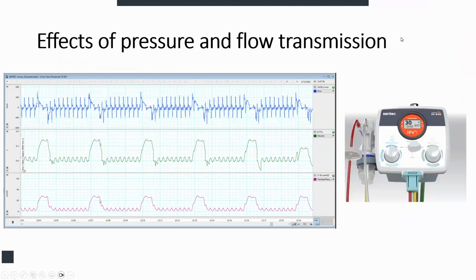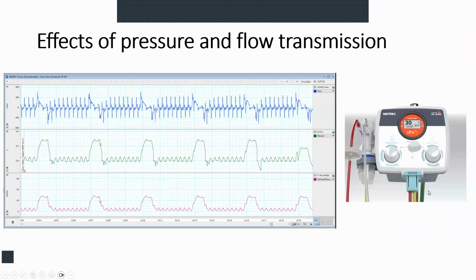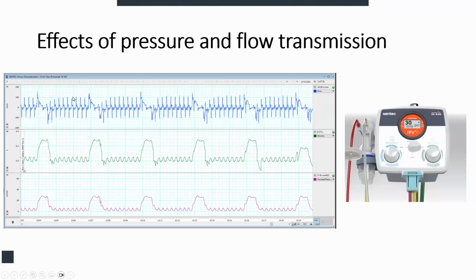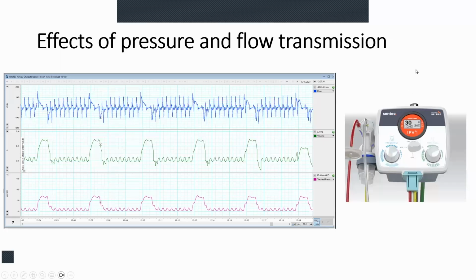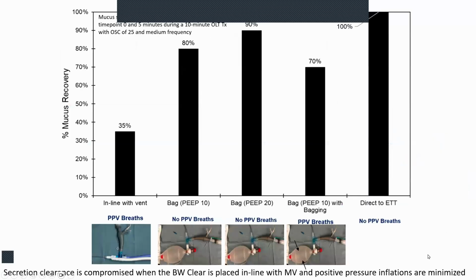And so when we consider even the IPV device, which is widely used in line with a mechanical ventilator, same thing. We don't really have the expiratory flow bias here. It plateaus because of the expiratory valve. There's massive attenuation in the pressure, and those oscillatory volumes are negligible. So how effective can they be in removing the secretions?